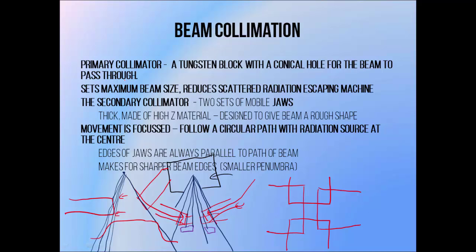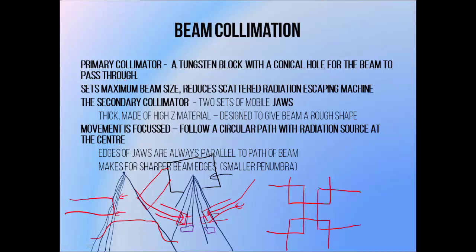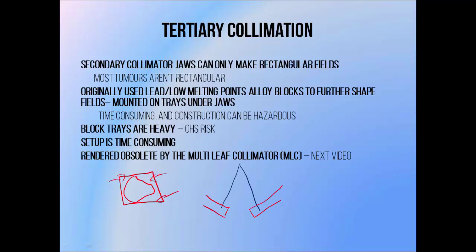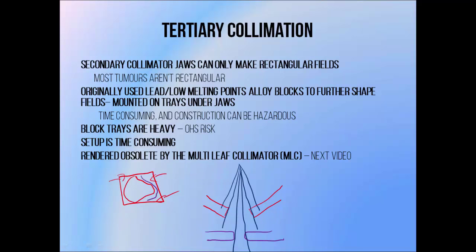There's also a third layer of collimation beneath the secondary collimator jaws, which we call the tertiary collimator. Secondary collimator jaws can only handle rectangular fields, and most treatment targets aren't rectangular, which can result in a lot of dose being delivered to tissues outside of the target without further collimation. Originally this was achieved using lead or low melting point alloy blocks to shape the beam, placed on trays beneath the secondary collimator jaws and arranged to block the field into the required shapes — either generic blocks or custom shapes cast on site. Generic blocks aren't terribly precise, but they're better than using the jaws alone, and making custom blocks can be time consuming and hazardous because it involves working with potentially toxic fumes.